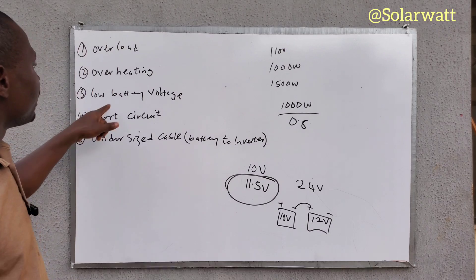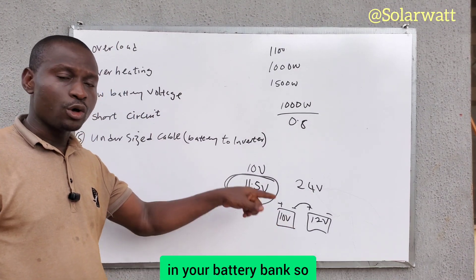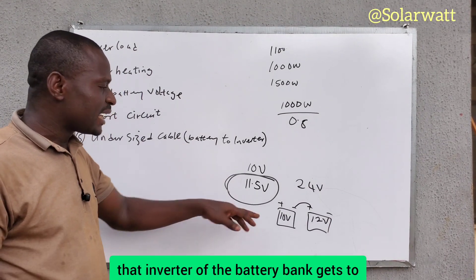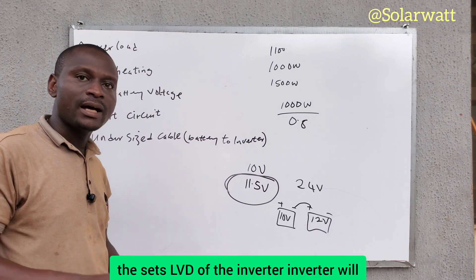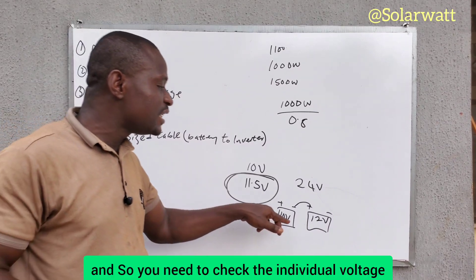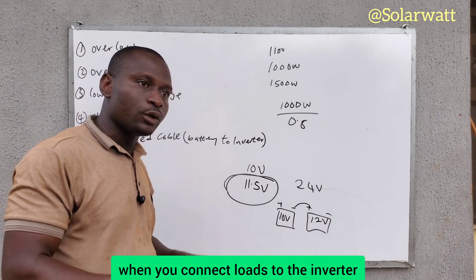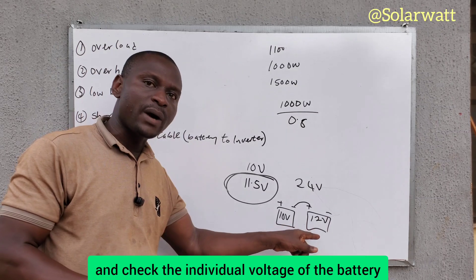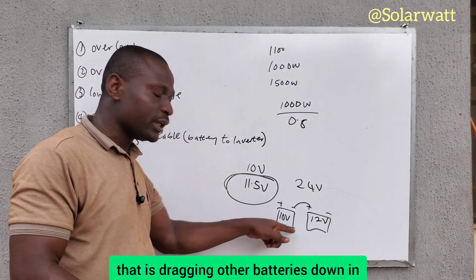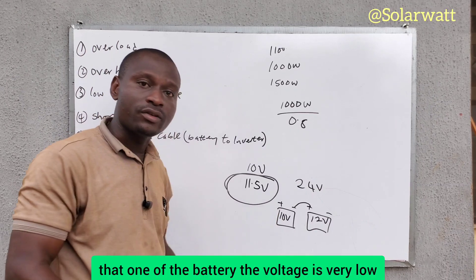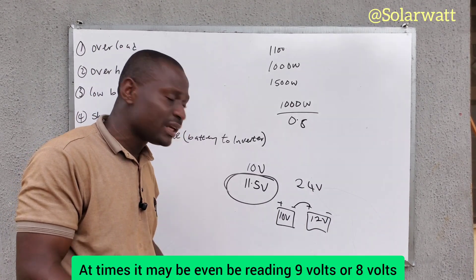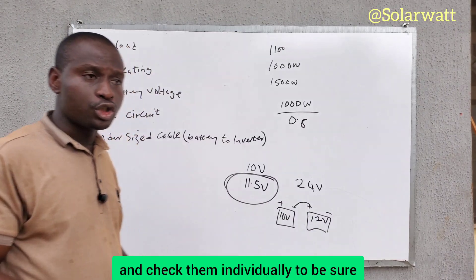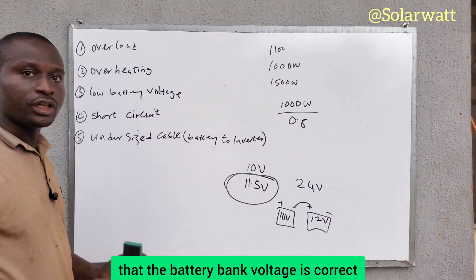The inverter will keep shutting down because it is detecting low battery voltage in the bank. When the battery bank voltage reaches the set LVD of the inverter, it will definitely shut down. Use your multimeter and check the individual voltage of each battery while the inverter is running with loads connected. This helps you identify the battery that is dragging the others down — it may be reading 9 or 8 volts while the others are still high. Check them individually to confirm that the battery bank voltage is correct.